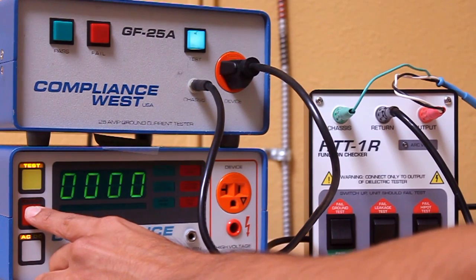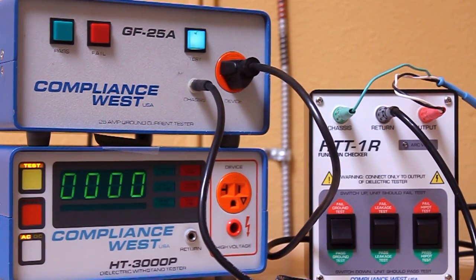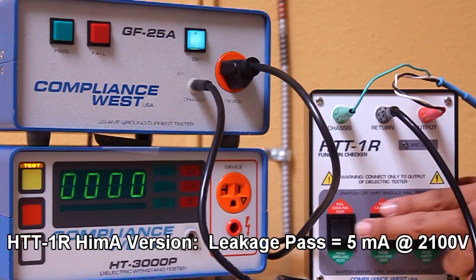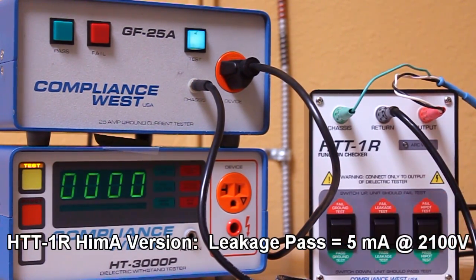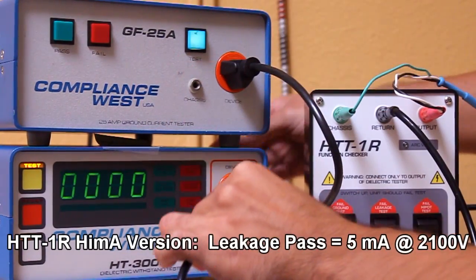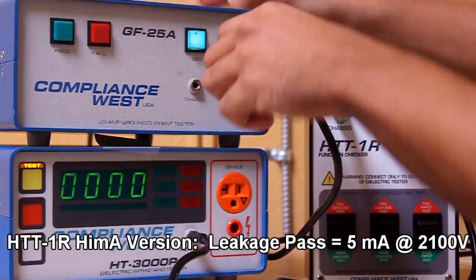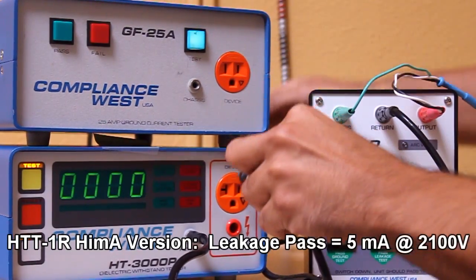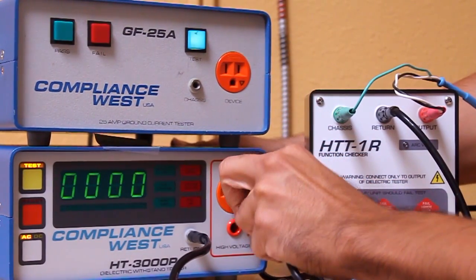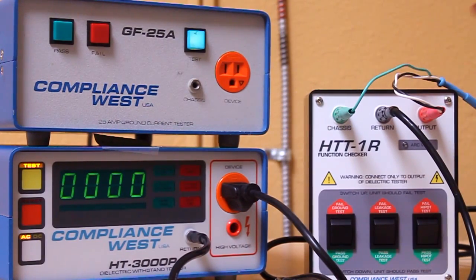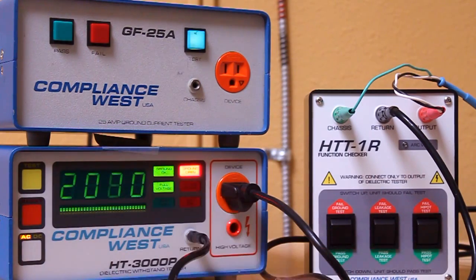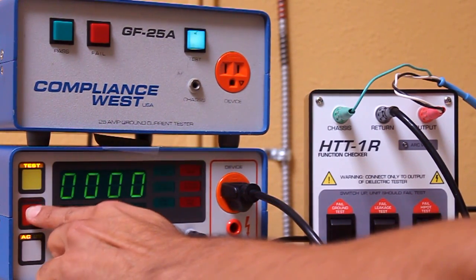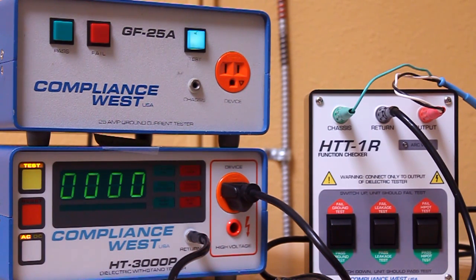Now we will connect the HTT-1R with all switches set to green to simulate a passing product. In the case of the HTT-1R HiMA tester, the Hipot tester is presented with a passing load corresponding to 5 milliamps of leakage current, which still exercises the tester to ensure that it can develop 5 milliamps and indicate a passing result. As you can see, all lights on the Hipot are green and the product has passed the test.